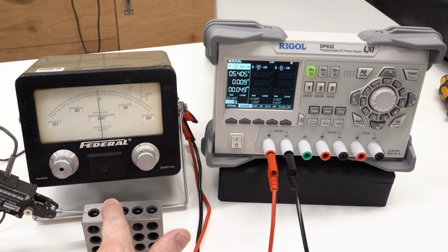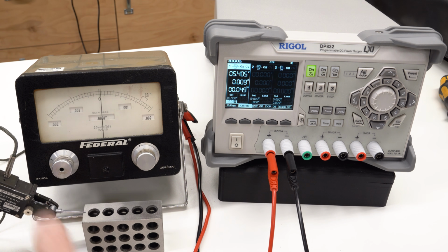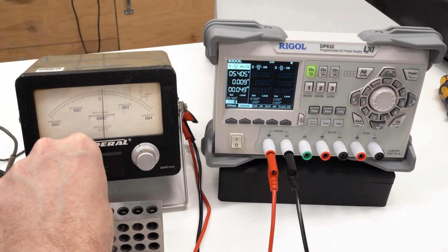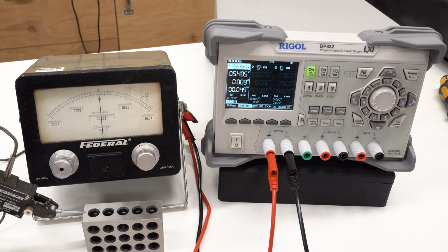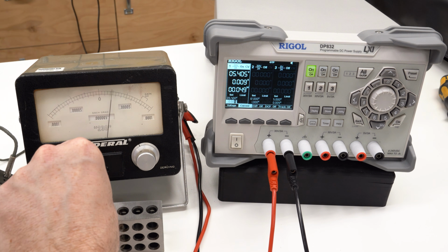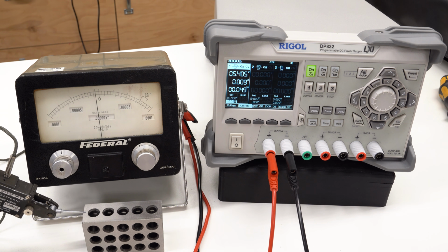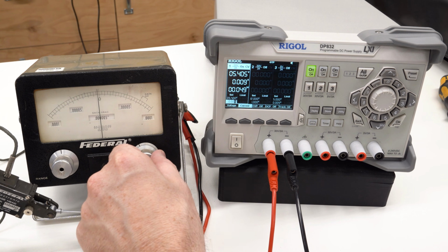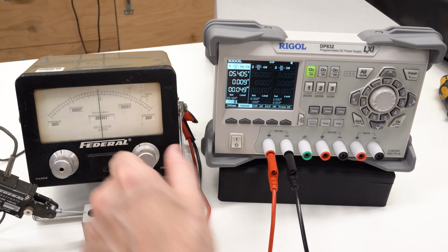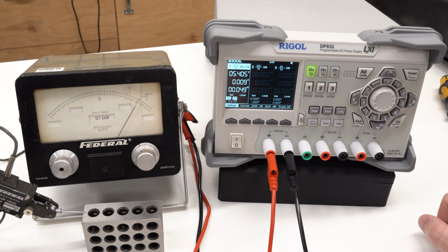If I press on the table surface or on the block or on the gauge head, we are getting needle movement. That seems plausible. Let's try the other ranges. Here's the middle range. It's still zeroed, and we're seeing more movement, which is what one would expect. And the highest resolution range, me just leaning against the bench is affecting this. It's 5 millionths of an inch per division, so you would expect it to be pretty delicate. But the zeroing seems to work there as well.